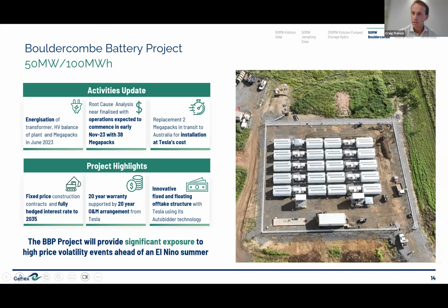The protocol is to allow the Megapack to burn itself out — you don't use water on lithium-ion batteries. You allow them to burn out, and that's the design implemented for this unit in particular, and it really behaved according to design. The fire was contained to the specific unit and burnt out in a controlled manner over a couple of days. It was really pleasing to see that it behaved as it was supposed to.